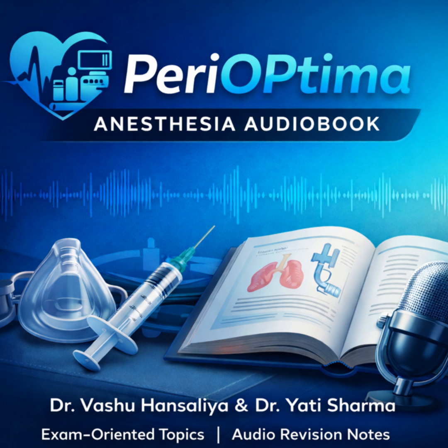The pump has the pharmacokinetic model, all that complex math embedded in its computer chip. It calculates exactly how much bolus is needed and what the infusion rate should be, adjusting it every few seconds to maintain that target. Now here is a distinction that I think confuses everyone. Plasma target, or Cp, versus effect site target, or Ce.